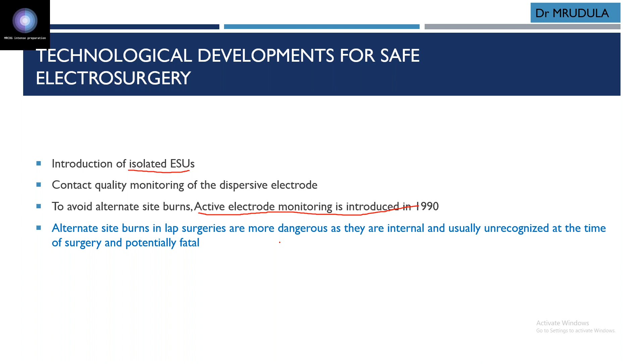Now, technologies which are developed for safe electrosurgery. Introduction of isolated ESU, so it should not be used with routine laparoscopic instruments. Contact quality monitoring of the dispersive electrode. To avoid alternate site burns, active electrode monitoring was introduced in 1990. Alternate site burns in lap surgeries are more dangerous because they are internal and usually unrecognized at the time of surgery, and they can be potentially fatal, like bowel perforation.